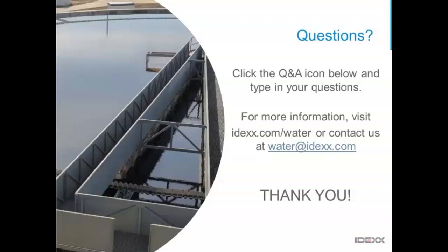Another one for you, Sean. Is it okay to use an air incubator instead of a water bath? If we're talking about fecal coliform testing, then we would highly suggest just focusing on the water bath, since the tolerance of 44.5 plus or minus 0.2 is really important. Unless you have a really good high-end air incubator, it's sometimes very difficult to maintain that plus or minus 0.2. So a water bath is best for fecal coliform testing.